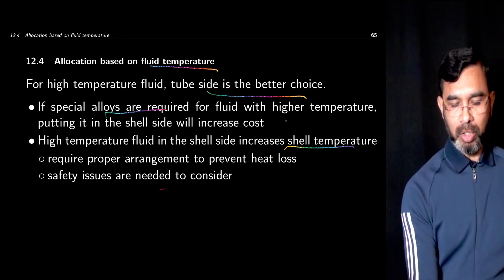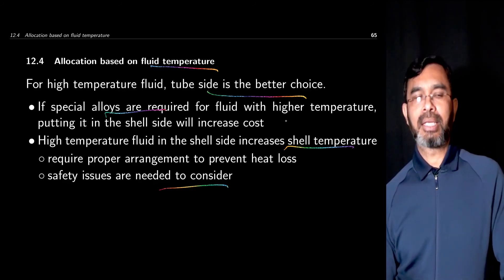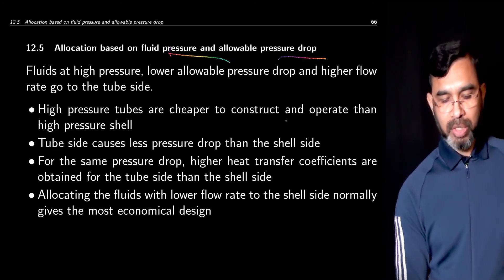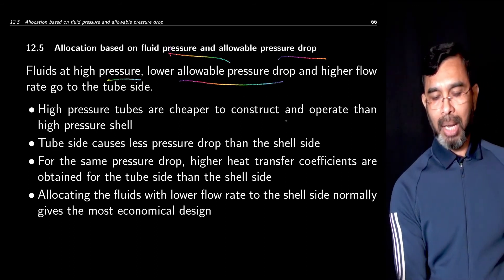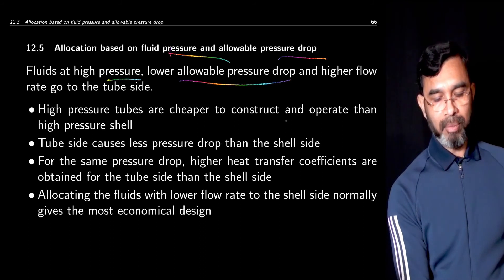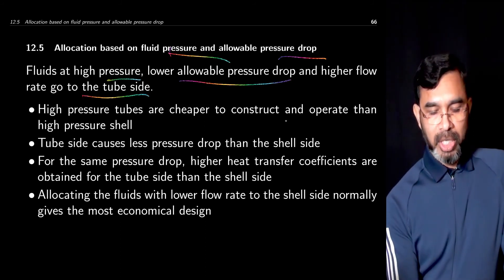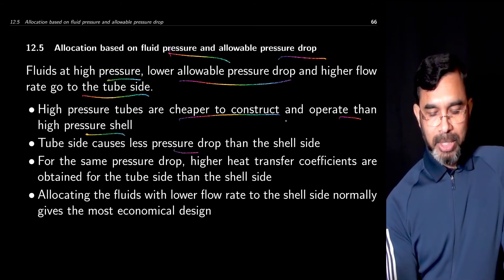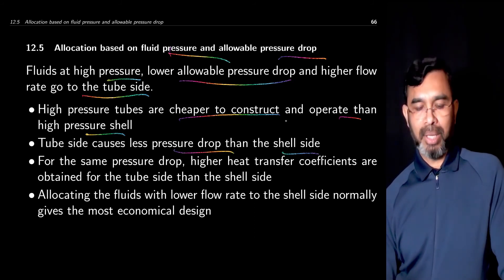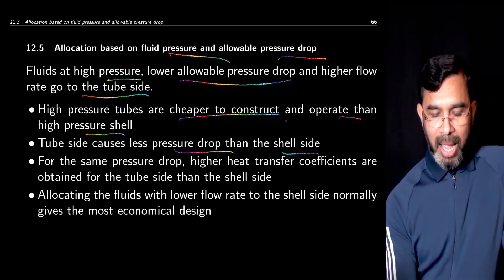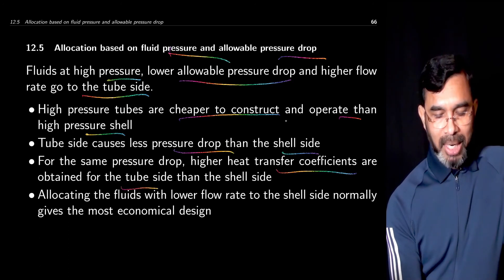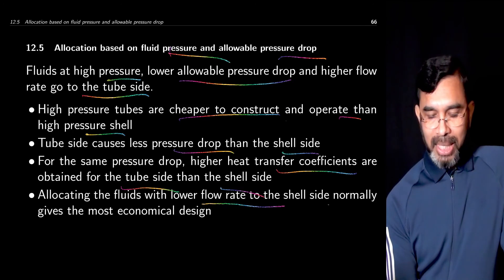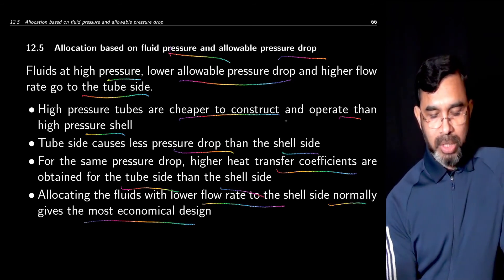Safety issues also need to be considered when the shell side is exposed to high temperature. Based on fluid pressure and allowable pressure drop, fluid at high pressure, with lower allowable pressure drop and higher flow rate, goes to the tube side, because high pressure tubes are cheaper to construct and operate than a high pressure shell. The tube side also causes less pressure drop than the shell side, and for the same pressure drop, higher heat transfer coefficients are obtained on the tube side. Allocating fluids with lower flow rate to the shell side normally gives the most economical design.